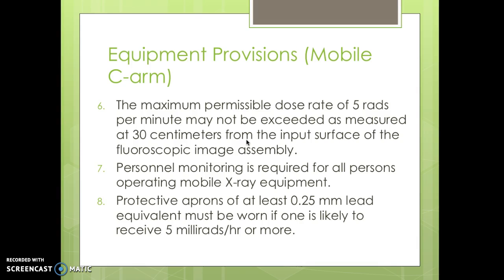The maximum permissible dose rate of 5 rads per minute may not be exceeded as measured at 30 centimeters from the input screen of the fluoroscopic image assembly. Personal monitoring is required for all persons operating mobile X-ray equipment, and protective aprons of at least 0.25 millimeters of lead equivalent must be worn if one is likely to receive 5 millirads per hour or more.